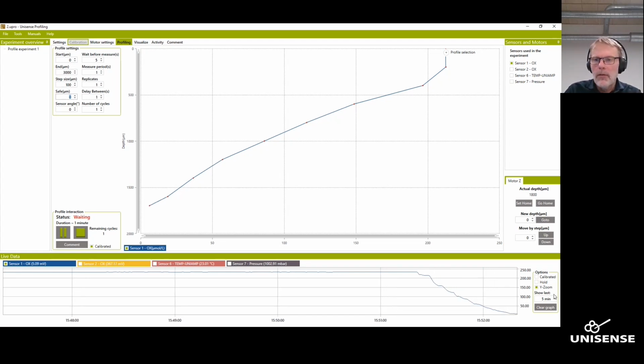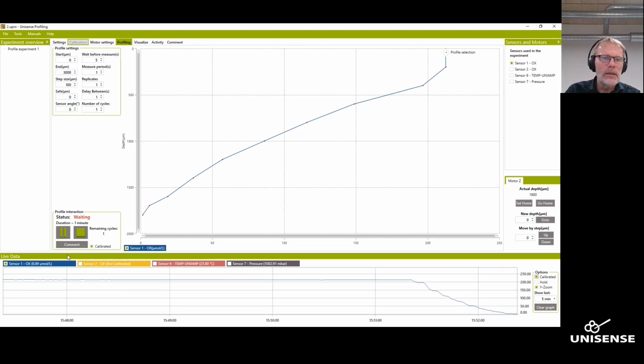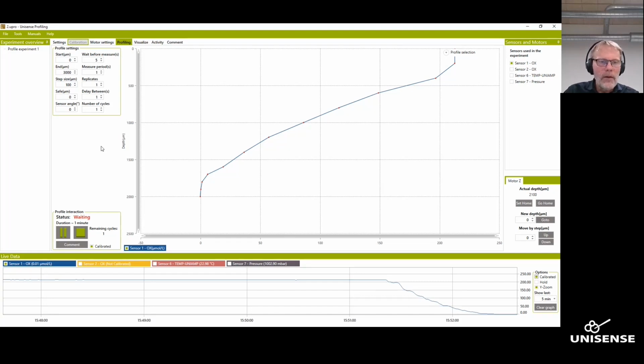If you choose calibrate down here, you can always see the concentration in micromoles per liter being shown. We are very close to 0 now. And then depending on how well you've defined your 0, see, I'm now a little bit below 0, and then minus 0.04 and so on. But now the profile becomes vertical. That means that we are now in the anoxic part of the sediment. There's no changes anymore as we go deeper. So there's no reason to go any deeper. So you can just click the stop profiling.